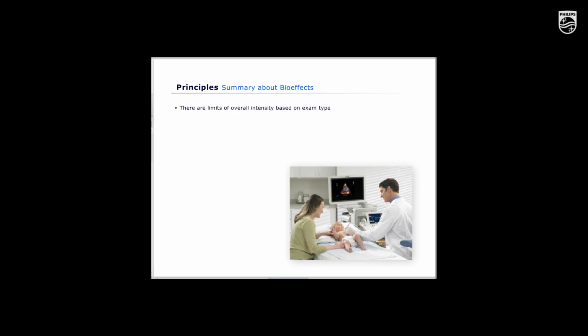A couple of last points about bioeffects. First is, based on the exam type, there are limits of overall intensity. Second, it is very important to select the appropriate exam type and preset when scanning a patient. Selecting the wrong preset may unnecessarily expose the patient to higher intensities of ultrasonic energy.